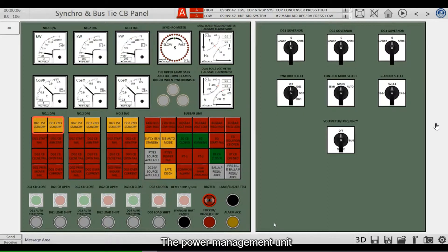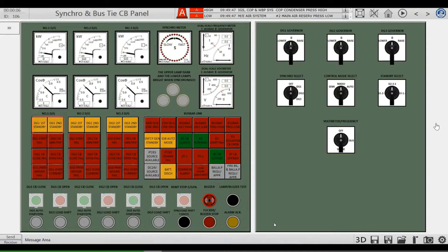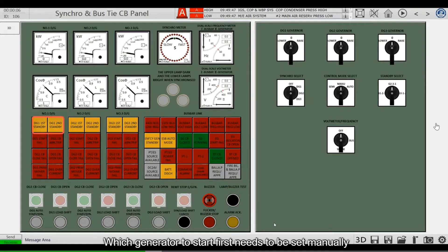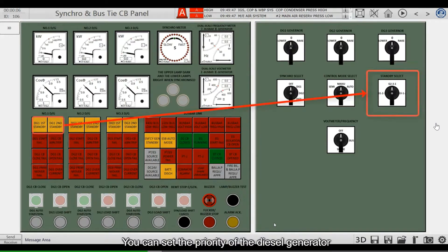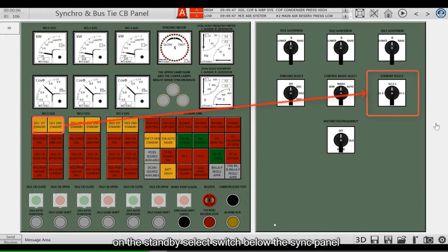The power management unit will issue a start order to the first generator. Which generator to start first needs to be set manually. You can set the priority of the diesel generator on the standby select switch below the sync panel.